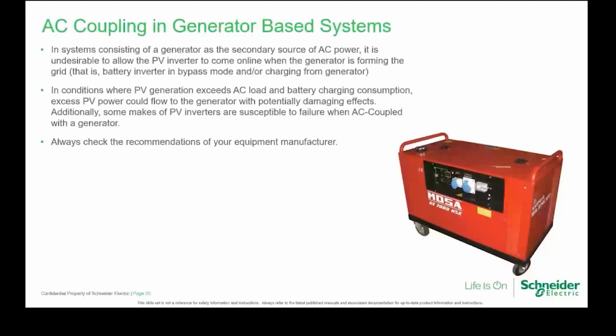When the PV generation exceeds the AC load and the battery charge consumption, as I said before, power could flow back to the generator with damaging effects. And make sure you always check the recommendations of your equipment manufacturer to make sure that it will be suitable.